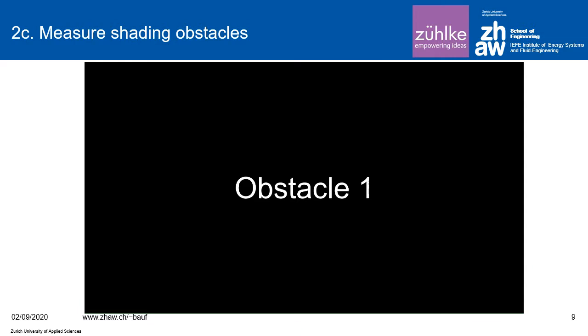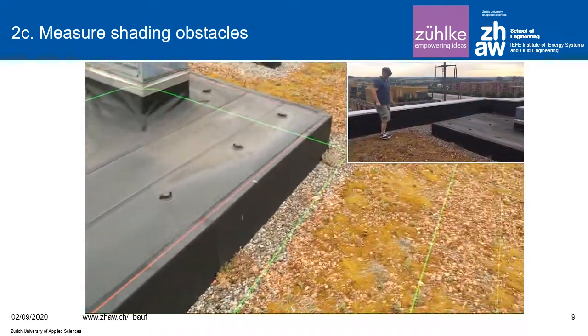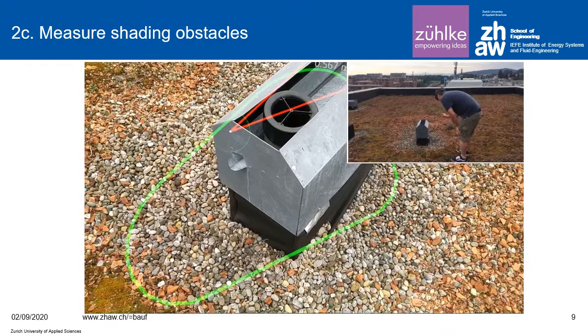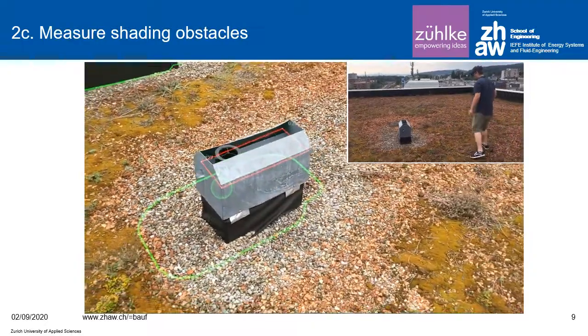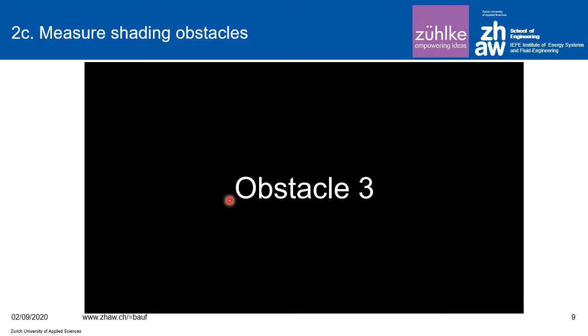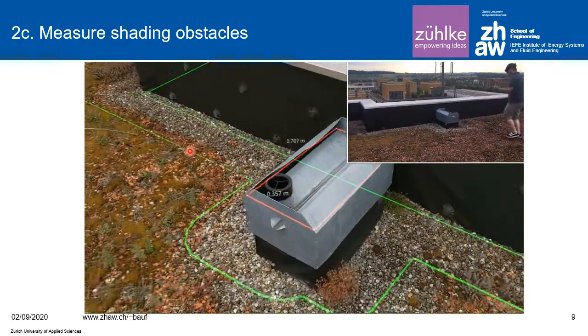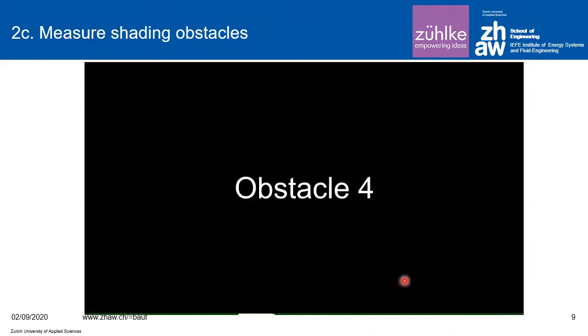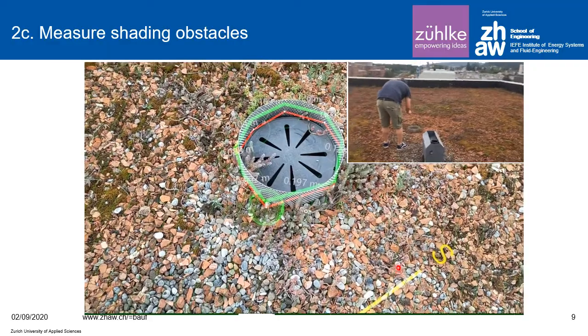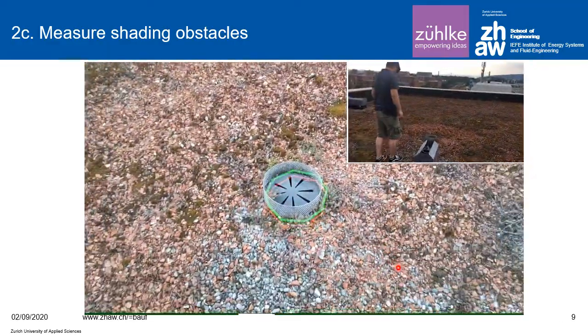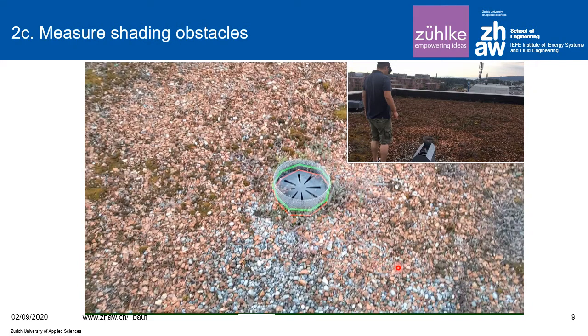Within task 2, we are now measuring the obstacles which lead to shading. We always have to find the top plane — typically four corners on the red top plane which causes shading. The green border line shows the edge where PV modules can be placed. After the fourth obstacle is measured, we note that real roof conditions don't always match the architect's plans, so real measurement is a must before installing a PV plant.